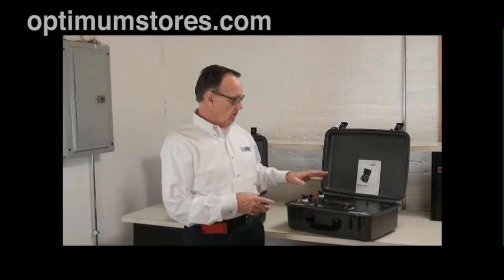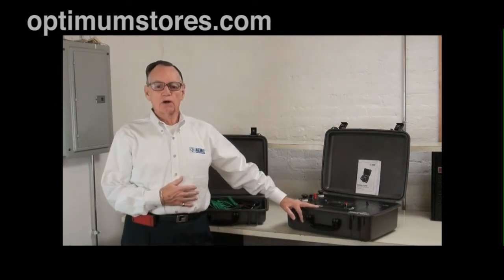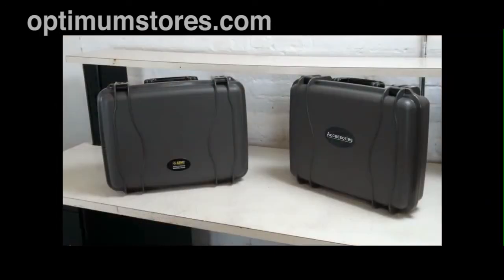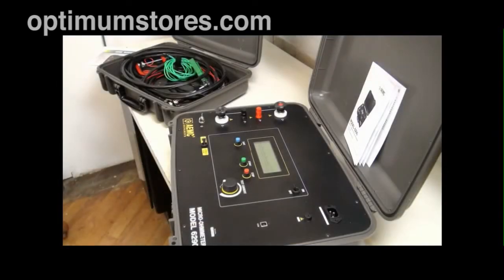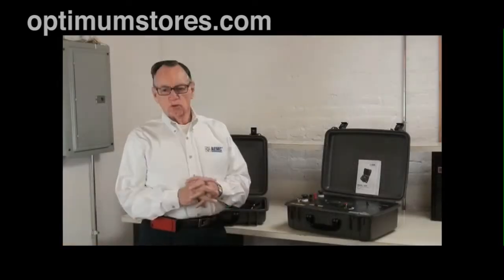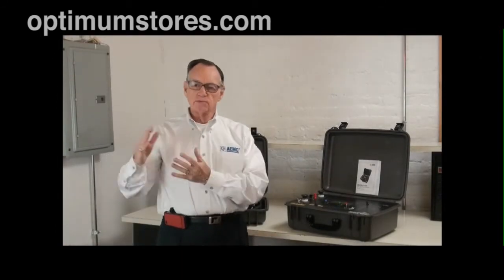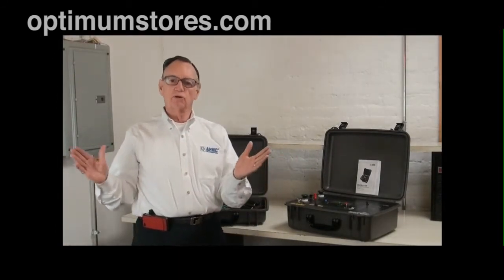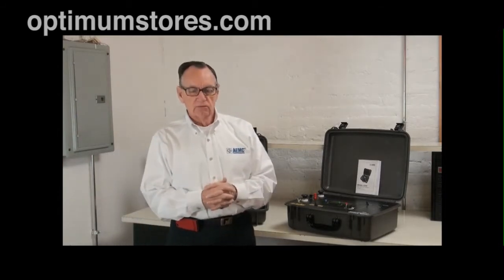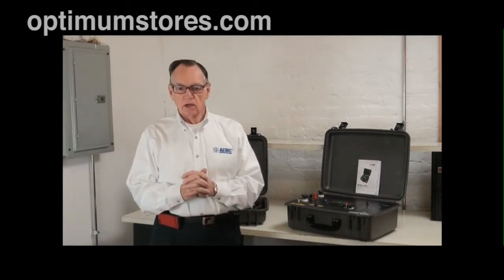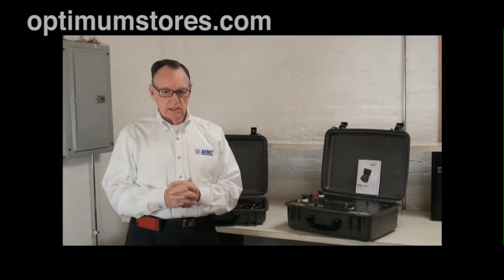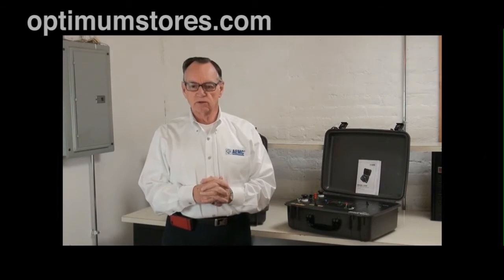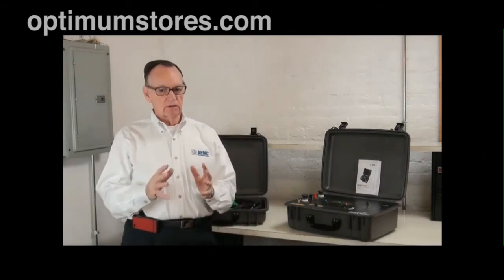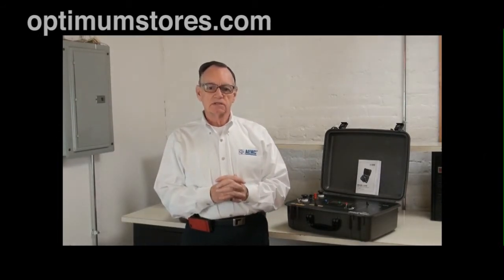Today we're going to talk about our latest model 200 amp micro-ohmmeter, model 6290. And what we have here is a device that can measure resistance down to 0.1 microohms, clear up to 20 milliohms, which gives us a good broad spectrum of measurements. The resolution is unprecedented at 0.1 microohms. Accuracy, heretofore not available, is 0.5% of reading, not of scale, of reading, which is a significant difference.